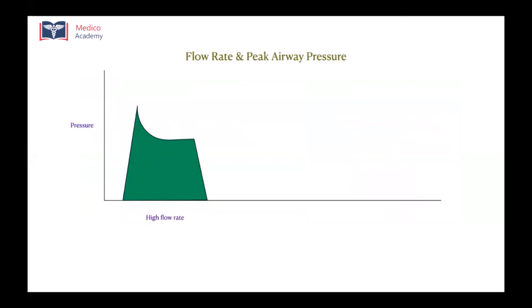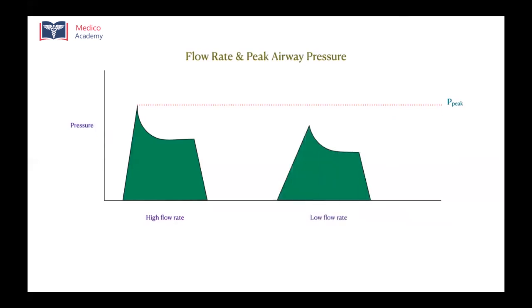So this is a simple graph. It is a pressure time graph. The pressure is on the vertical axis and time is on the horizontal axis. So this is a high flow rate where you can see that this is the P peak. Now we have reduced the inspiratory flows to the patient. So you can see that the slope of the graph reduces. That is, the flow rate has reduced, and that has resulted in a lower peak airway pressure. So that was what was discussed in the previous table.